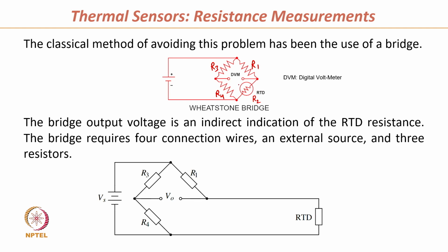Now, this is the conventional way of removing this error, where this RTD is exposed to the body temperature which is from outside, and all the other resistances are not exposed. This RTD is made of platinum. It will give a linear change in the resistance when subject to this TB, and this we can detect using this bridge. But when we expose this RTD to some temperature, we need to keep it separate from the other assemblies or the other resistances, because these resistance also has some temperature dependency. So, still we connect this RTD which is far away from the whole assembly. This is whole assembly, we do not want to expose to different temperature.